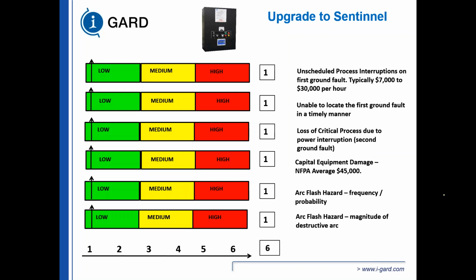Being unable to locate the first ground fault in a timely manner is not an option. We can locate it very quickly, and we could typically locate a ground fault with this system in less than an hour in any size facility.